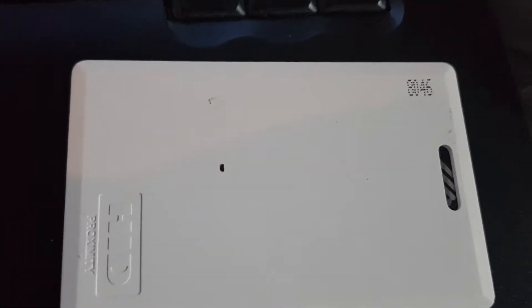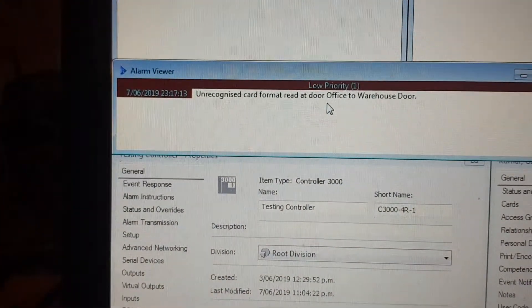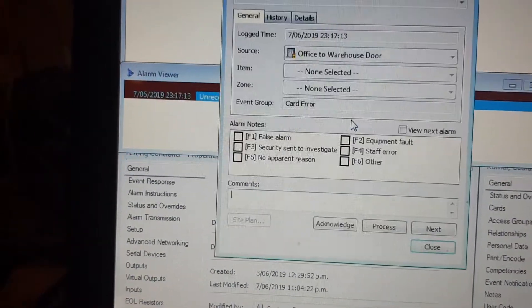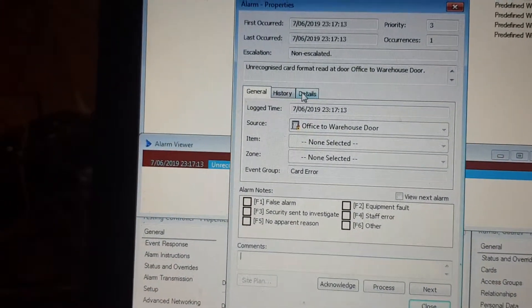I've got a third party reader connected into a Cardax controller and I have this HID prox card — the number on the card is 8046. If I badge this card against the reader, an alarm comes up in the alarm viewer as an unrecognized card format.